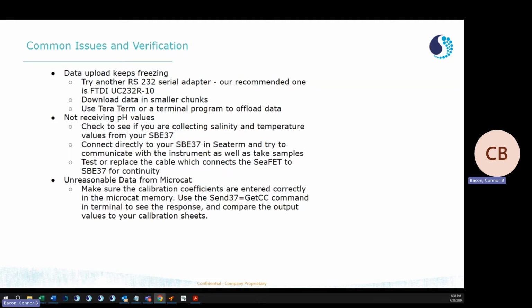Finally, if you're getting unreasonable data from your MicroCAT, make sure the calibration coefficients are entered correctly in the MicroCAT memory. Use the send37 equals getCC command in terminal to see the response and compare those output values to your calibration sheets. If you ever have questions about your data or with our software, reach out to us directly and we will be happy to get you back on track.